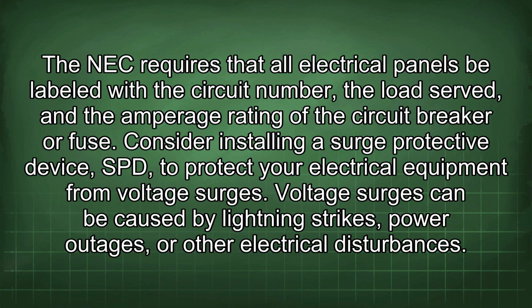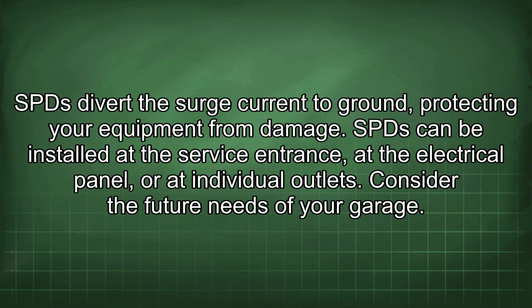Consider installing a surge protective device, SPD, to protect your electrical equipment from voltage surges. Voltage surges can be caused by lightning strikes, power outages, or other electrical disturbances. SPDs divert the surge current to ground, protecting your equipment from damage. SPDs can be installed at the service entrance, at the electrical panel, or at individual outlets.